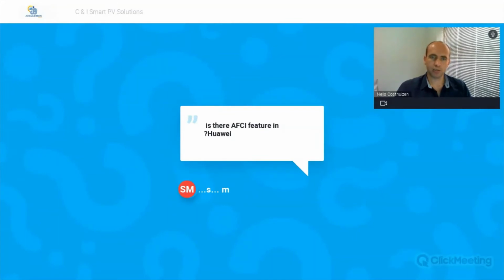Is there an AFCI feature in Huawei? Yes. The arc fault circuit interrupter is featured in the Huawei inverters. Please note that it is specific to the newer range of inverters. If we look specifically at the 30, 36, and 40 kTL M0, the M0 range would not have the built-in AFCI, but the M3 range of those inverters do have it. And on the 100 kTL, it is built in. The AFCI on the 100 kTL would be the M1 Pro version. So just double check in your country or region with your sales representative. Reach out to them to confirm that it's built in or that they are selling the correct model. But yes, the AFCI feature is available in Huawei inverters.